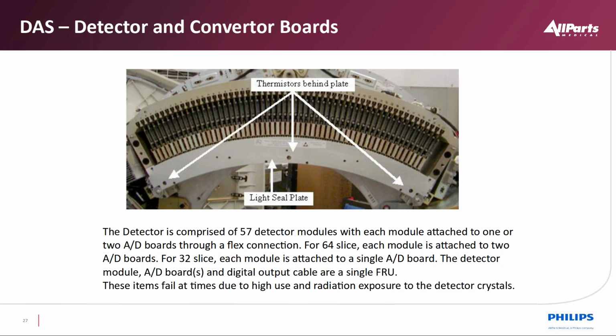So this is an example of a detector. What's not seen here behind this metal plate is actually the detector crystals. They're kind of behind the plate here, but these are the converter boards behind it that receive our detector data and then convert it into A to D, and we have a number of rows. So this one has an example of 57 modules. Some of the modules in the center will probably have a tighter spec than the ones towards the outer edges. So they might be graded like A, B, C, regards to the detector functionality and which ones go where, okay?